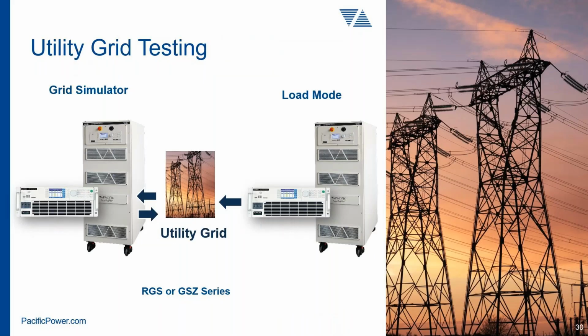They simulate the grid; worldwide grid combinations of voltage and frequency can be simulated at different power and current levels, also parallelable, of course. And electronic load mode options are available on these products as well. So they can be used as an electronic regenerative load, which is particularly energy efficient, because about 90% of the power you're dumping into the load will be recovered to the grid. So your energy cost will be significantly lower than when you use dissipative loads, traditional resistive type loads.